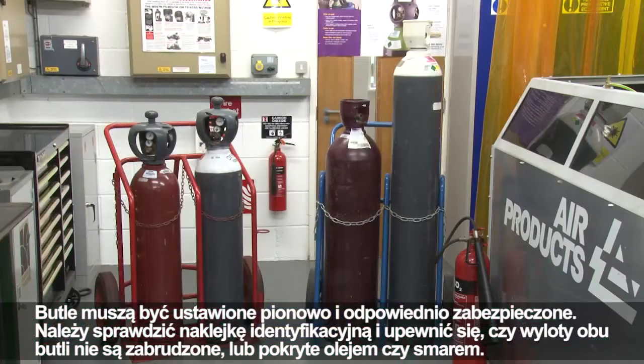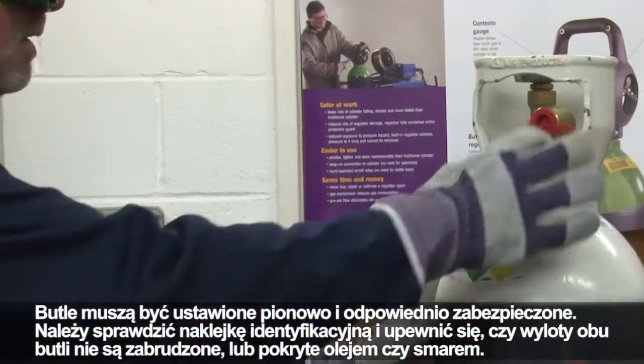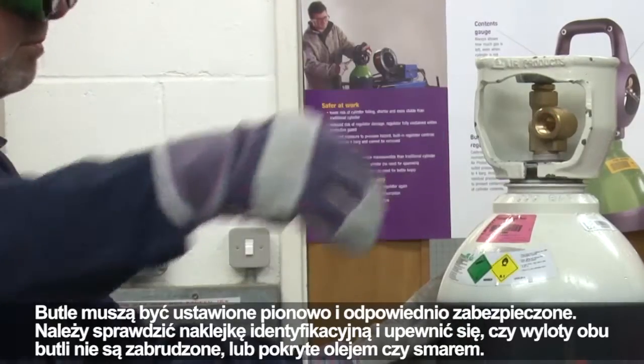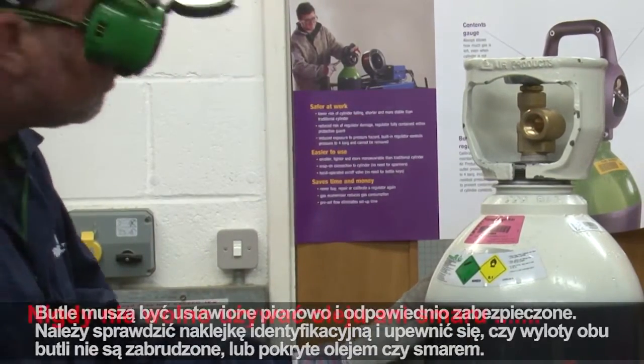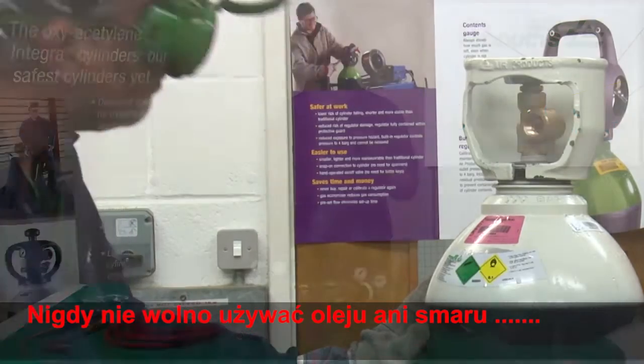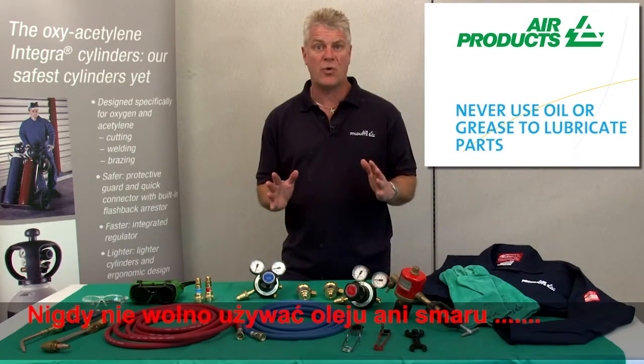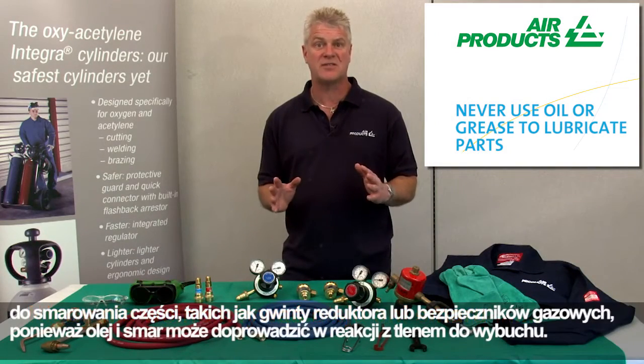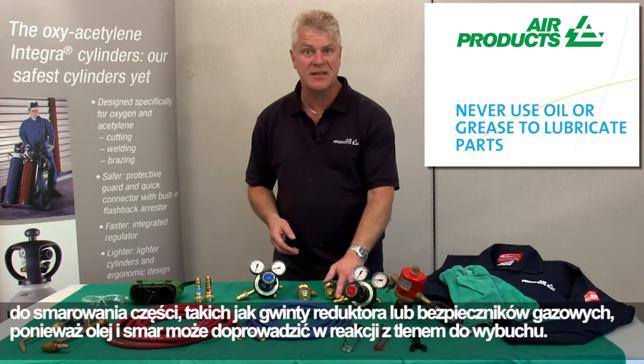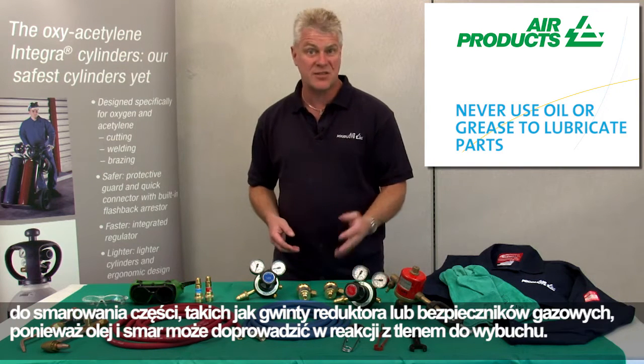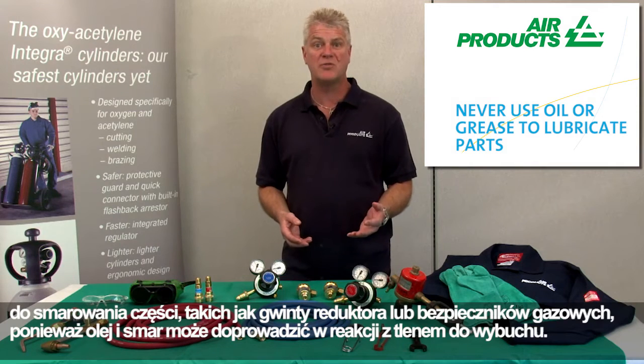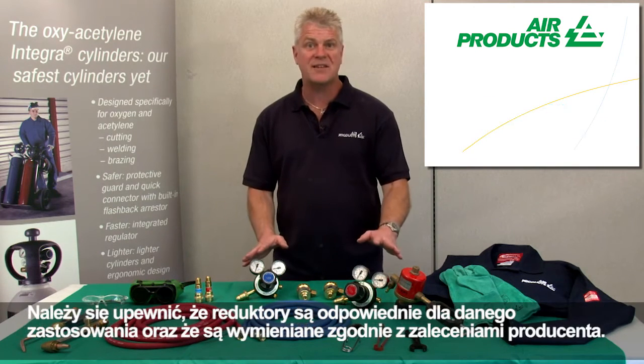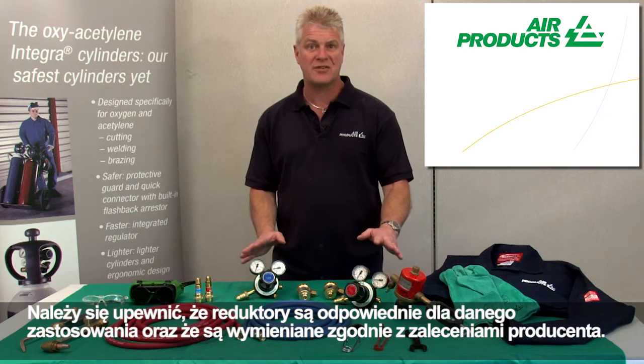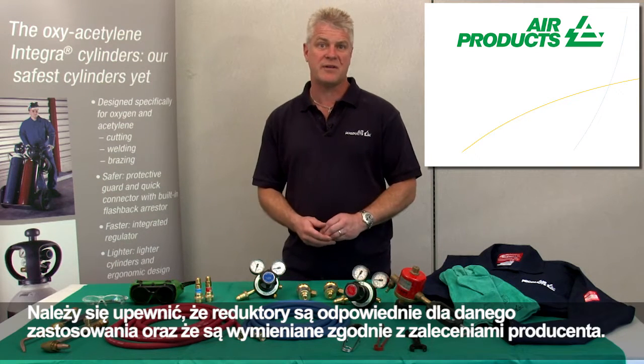The cylinders must be upright and secured. Check the identification label and check the outlets of both cylinders are clear of dirt, oil or grease. We cannot repeat this enough. Never use oil or grease to lubricate parts such as the threads on the regulator or the flashback arresters, as oil and grease can cause an explosion reacting with oxygen. Ensure that regulators are fit for purpose and within manufacturer's recommended replacement period.